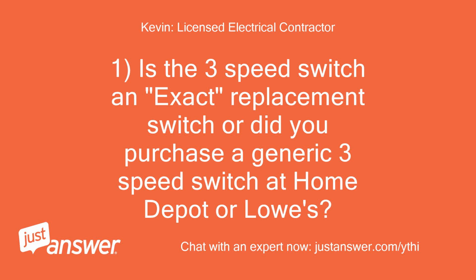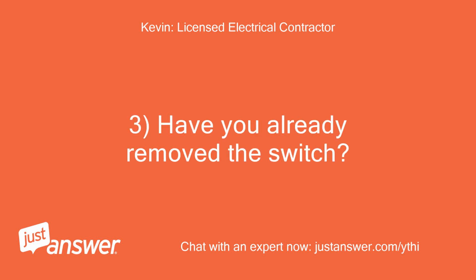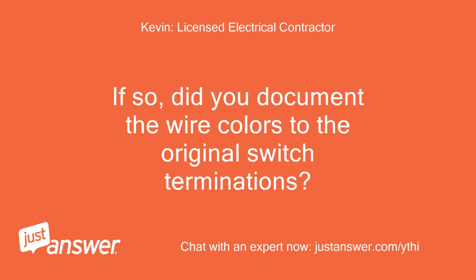1. Is the 3-speed switch an exact replacement switch, or did you purchase a generic 3-speed switch at Home Depot or Lowe's? 2. What are the 4 wire colors for L, 1, 2 and 3? 3. Have you already removed the switch? If so, did you document the wire colors to the original switch terminations?